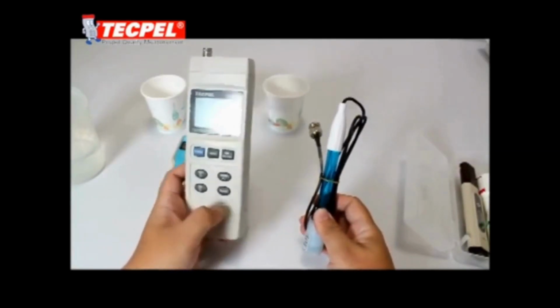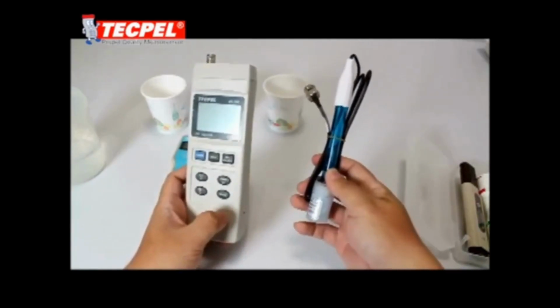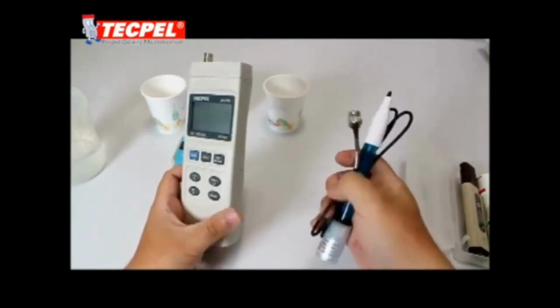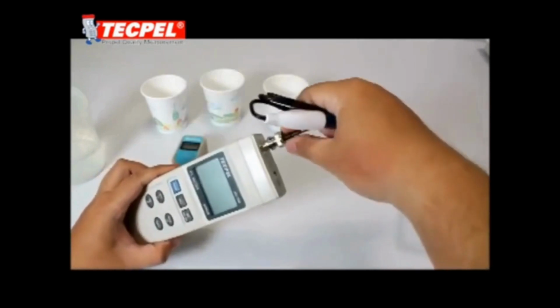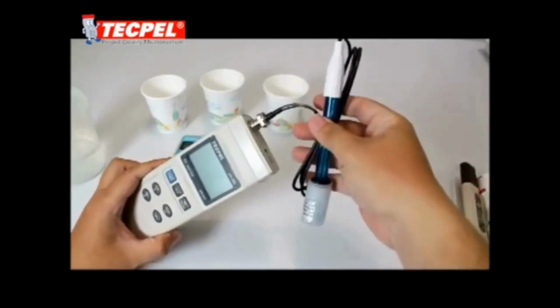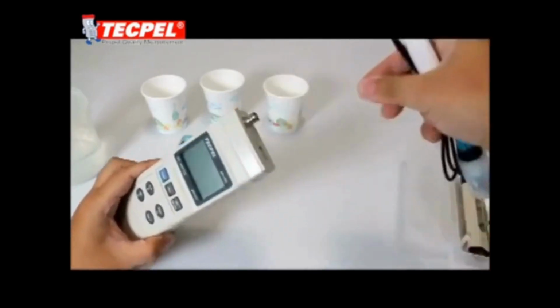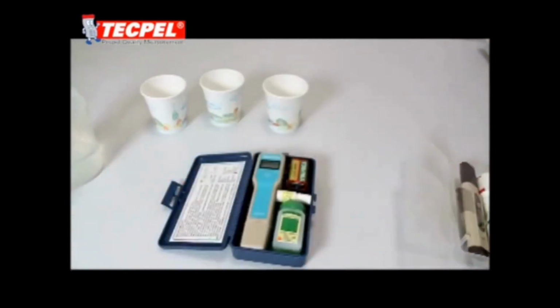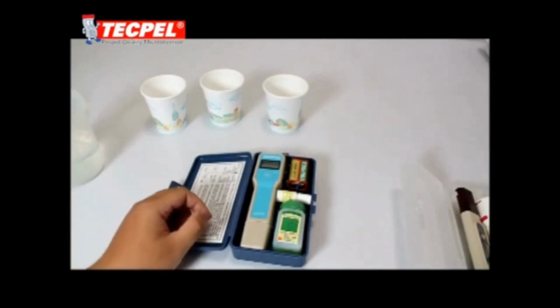The second type of pH meter is the separated design. In this style, the host unit and the sensor are two independent pieces. Users can choose different sensors based on their needs, such as sensors for liquids, gels, soil, or high-precision use. The sensor must be installed before measurement, but this design provides much more versatility.